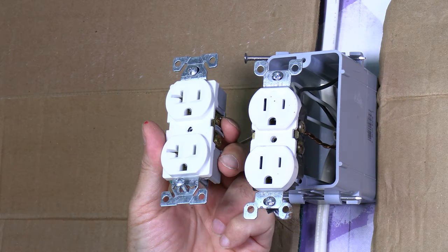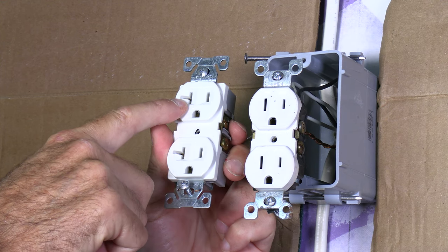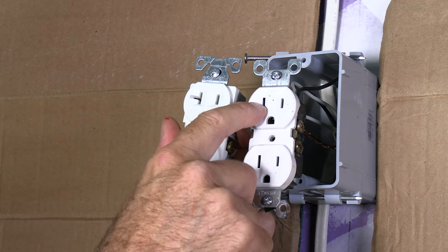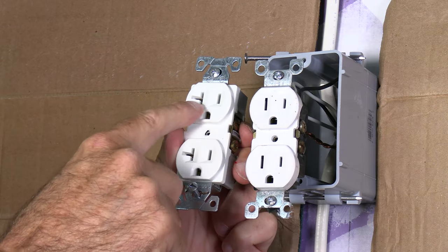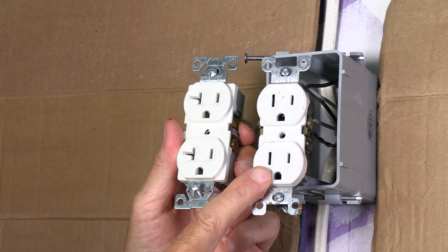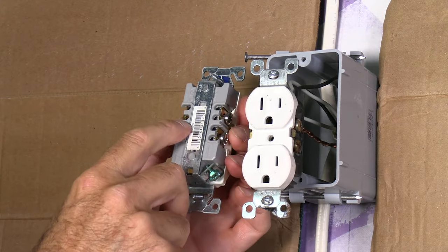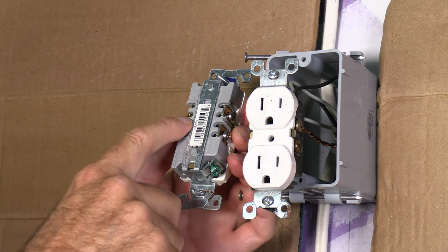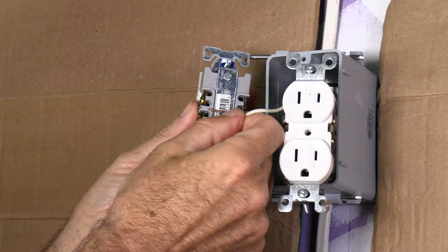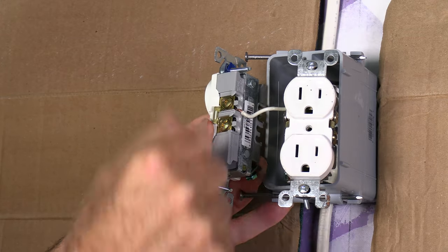And as I was saying earlier, use this device right here to verify that your plugs are right. If you're not sure you've got two different types of plugs here. If you notice this one has this mark to the side here, this indicates that this is a 20 amp outlet. This one doesn't have it. This is a 15 amp outlet. I have seen this so many times. They'll put in this type of an outlet on a 20 amp circuit and I see it all the time. And to me it's wrong. So the 20 amp outlets usually have a different type of clamp on the back of it. This one you can put the wire straight into like so. It works just like that.